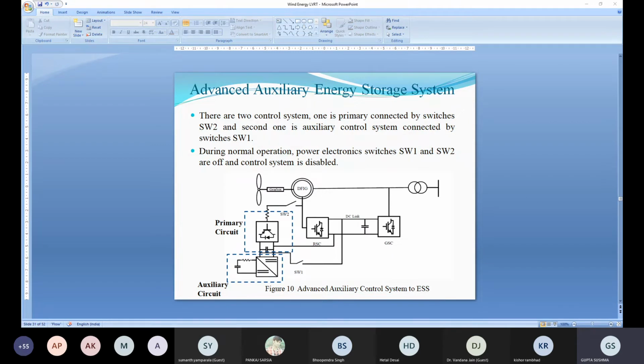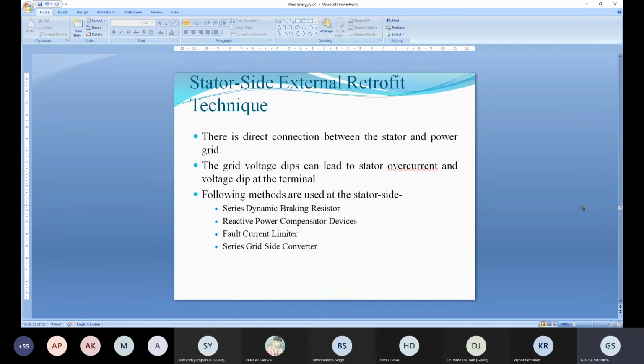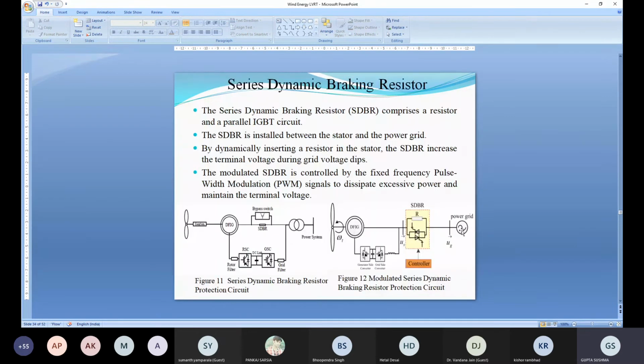These are the methods to protect the rotor or DC link, where we connect the circuit at the rotor side. Next is the stator side external retrofit technique, where we connect the circuit at the stator side. So the techniques are series dynamic braking resistor, reactive power compensator, fault current limiter, and series grid side converter. These are the different techniques which we use at the stator side.